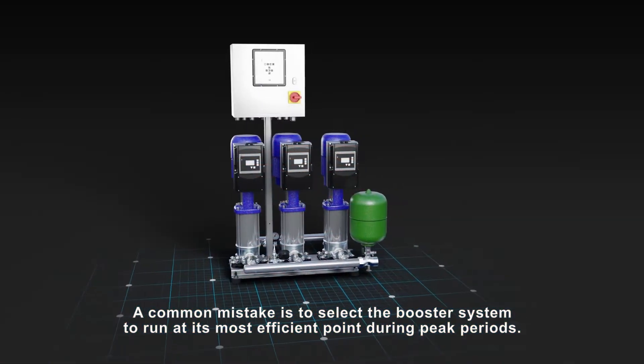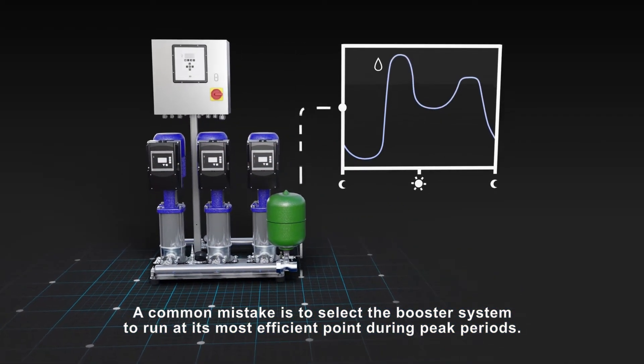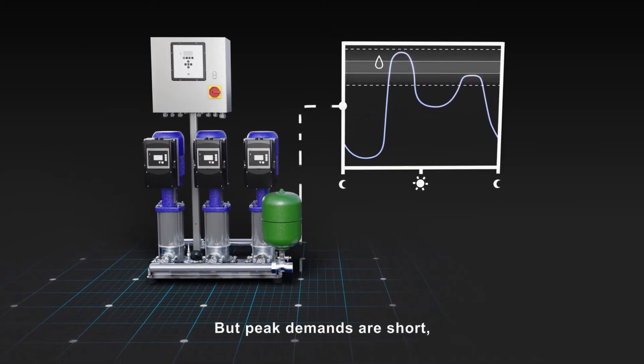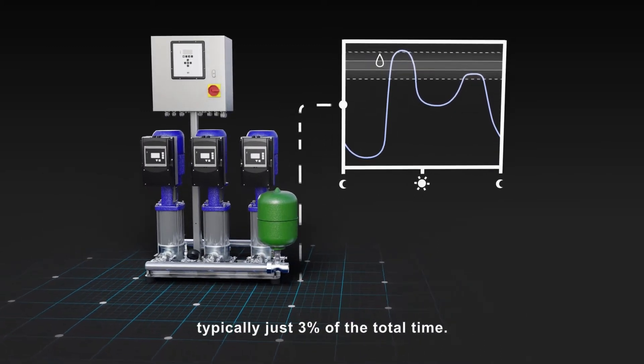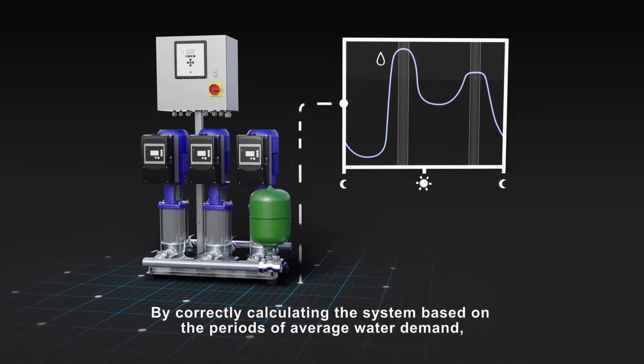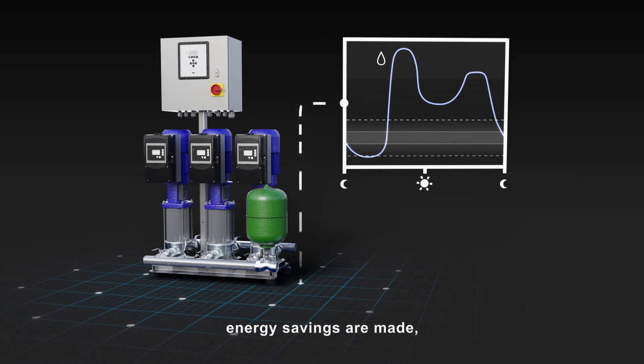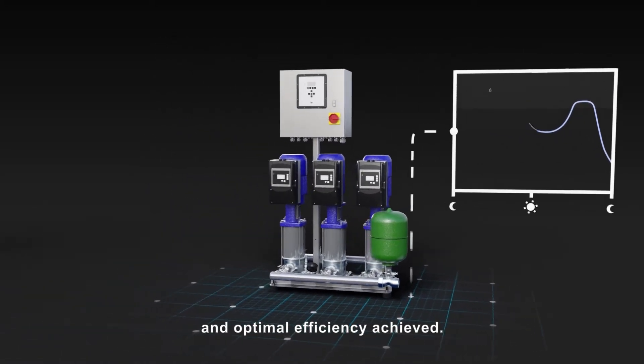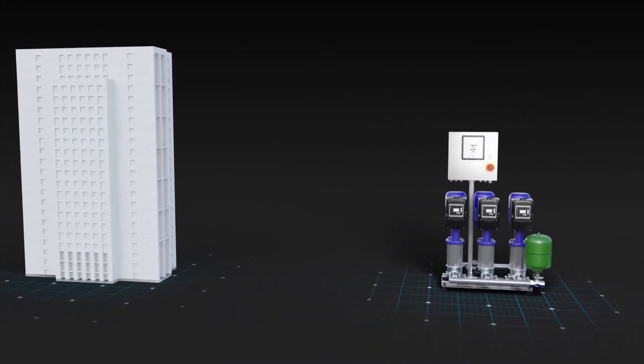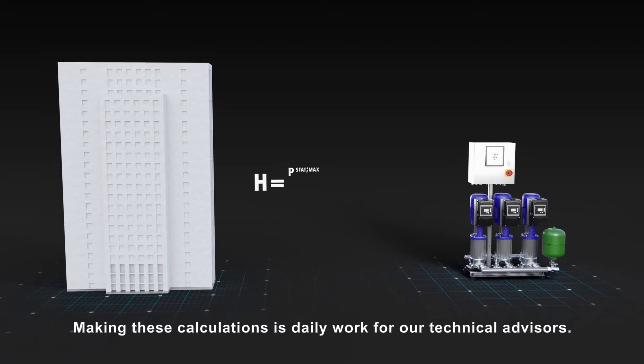A common mistake is to select the booster system to run at its most efficient point during peak periods. But peak demands are short, typically just 3% of the total time. By correctly calculating the system based on the periods of average water demand, energy savings are made, peak time water pressure delivered and optimal efficiency achieved. Making these calculations is daily work for our technical advisors.